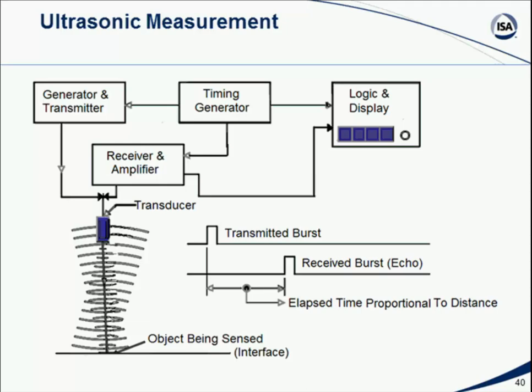The speed of sound through a gas or fluid is not fixed. It's going to depend on the density and the temperatures and such, but it can be corrected for. If we make a sound pulse and send it through liquid or gas, and it hits a surface, it's going to bounce back. So if we start a timer going from when we transmit the sound pulse and count when we hear the echo, so we hear our hello back, by counting precisely the time difference, we can compute the distance from our transmitter device to the surface we're measuring. So it's a distance measurement. In fact, if you used to have an old Kodak camera years ago, or Polaroid camera years ago, they used ultrasonic sound bursts to automatically focus the camera. Well, we use the same type of technology.